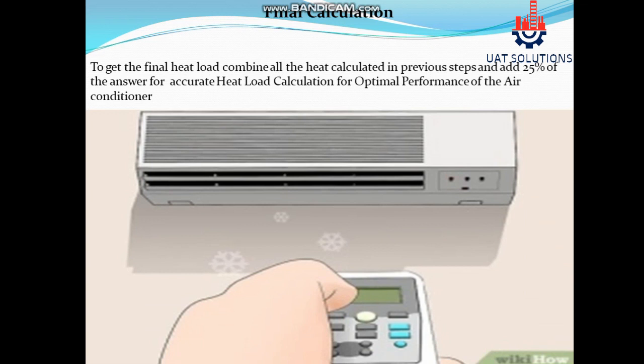Final calculation: to get the final heat load, combine all the heat values calculated in the previous steps, then add 25 percent of that total for an accurate heat load calculation and optimal performance of the air conditioner.